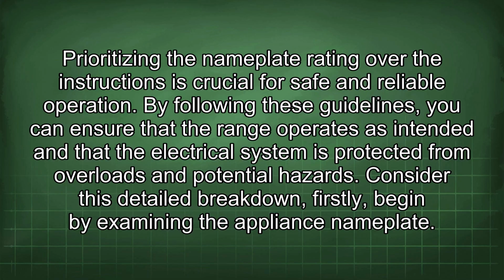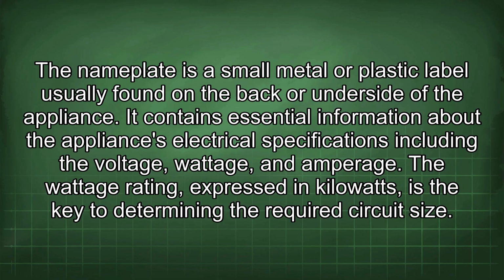Consider this detailed breakdown. Firstly, begin by examining the appliance nameplate. The nameplate is a small metal or plastic label usually found on the back or underside of the appliance. It contains essential information about the appliance's electrical specifications, including the voltage, wattage, and amperage. The wattage rating, expressed in kilowatts, is the key to determining the required circuit size.